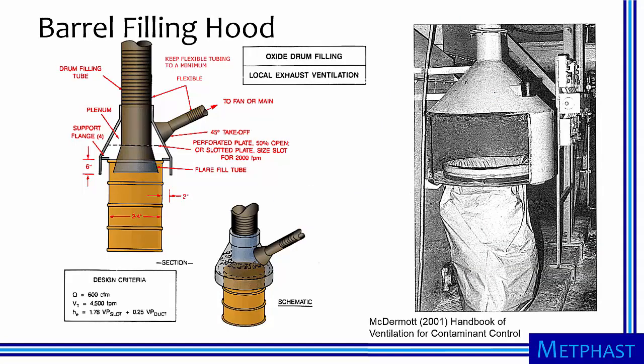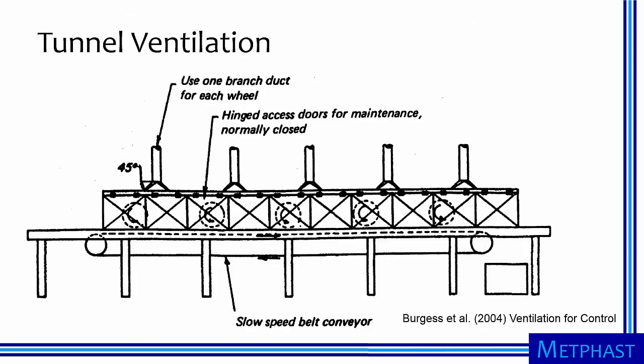There are numerous other examples of enclosing hoods. Here, a hood specifically designed for barrel filling is shown. When material such as a powder is dropped into a barrel, it displaces air in the barrel. If the material is dusty, the displaced air will contain many particles, and the barrel filling hood captures this particle-laden air before it enters the workplace. Another example is a ventilated tunnel, which fully encloses a dusty process such as grinding as parts move along a conveyor belt. The tunnel helps reduce the volume of air required to ventilate this type of process.